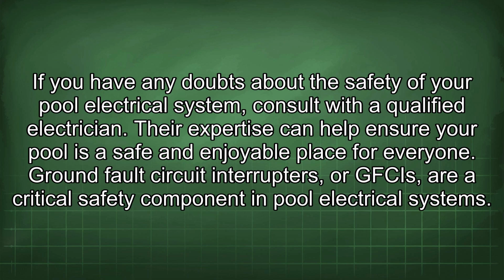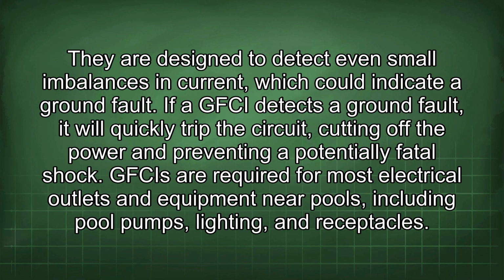Ground fault circuit interrupters, or GFCIs, are a critical safety component in pool electrical systems. They are designed to detect even small imbalances in current, which could indicate a ground fault. If a GFCI detects a ground fault, it will quickly trip the circuit, cutting off the power and preventing a potentially fatal shock. GFCIs are required for most electrical outlets and equipment near pools, including pool pumps, lighting, and receptacles.